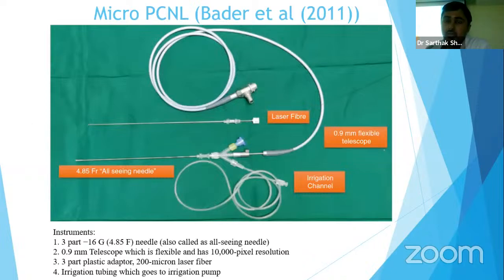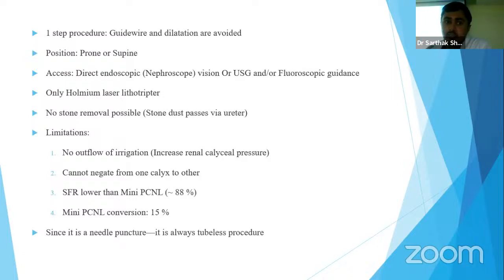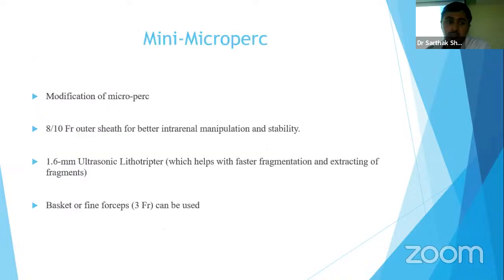Micro PCNL was given by Bader in 2011. It utilizes a 4.85 French all-seeing needle, which has 2 outlets, one for the laser fiber and one for the irrigation channel, and utilizes a 0.9 millimeter flexible telescope. Important here is the flexible telescope. It has a retrograde attachment because the needle cannot withstand the heavy weight of the instrument. It is a one-step procedure where dilatation and guide wire insertion are avoided and only laser lithotripsy can be used. Stones are not removed, only stone dust is made, which is passed via the ureter. Limitations: it may show increased renal calyceal pressure as there is no outflow of irrigation, and the stone-free rates are slightly lower, around 88%. It requires conversion to mini PCNL in 15% of the cases.